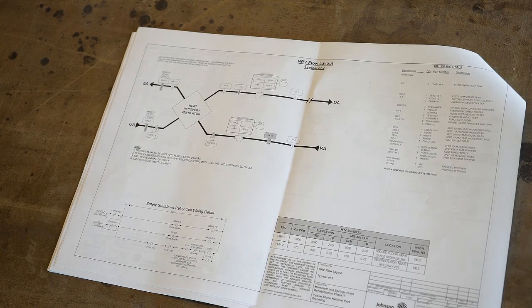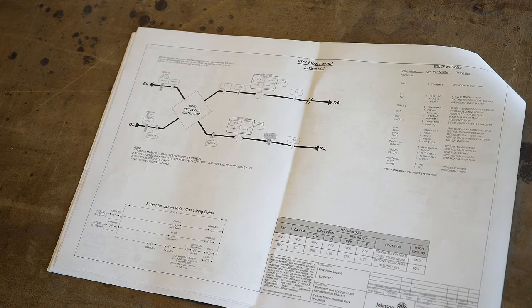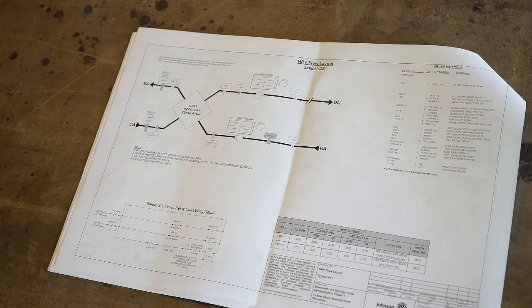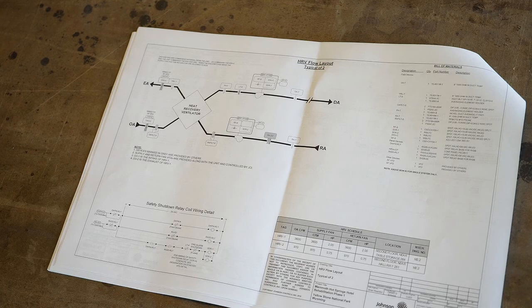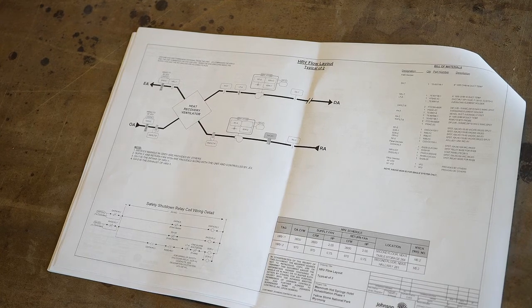Then we're sending a signal to the supply fan and the exhaust fan, and that was set by the test and balance, which is basically all at 100% on all the units. So we're commanding those fans to 100%, and then they're just doing their thing.